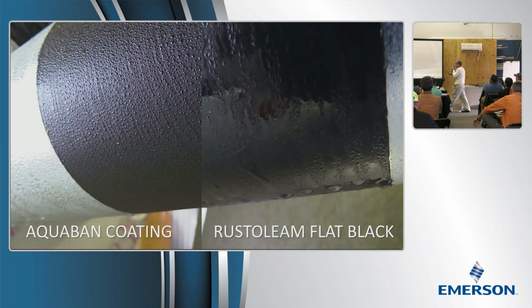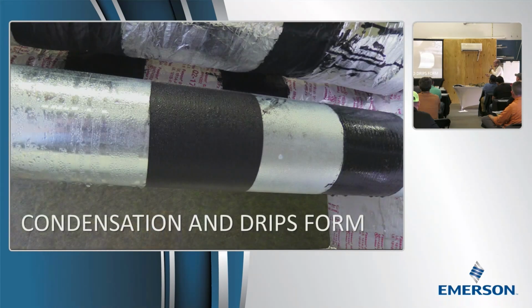What did we find? That yes, the Aquaban coating made a big difference. It can still sweat, so you can't say the Aquaban coating prevented condensation — it made it harder for it to sweat, you had to get it colder. Do you see the difference in how the beads of moisture formed? It didn't want to. I've also tried Never Wet — if you've used a two-part Never Wet on grills, it's the same thing. The grill still sweats, it's just so small you can't see it. You've got to get real close to see the little droplet because it's still sweating, just small. That's what we saw here — it couldn't prevent condensation, but it was particularly effective on ductboard. Worked really well on the ductboard.